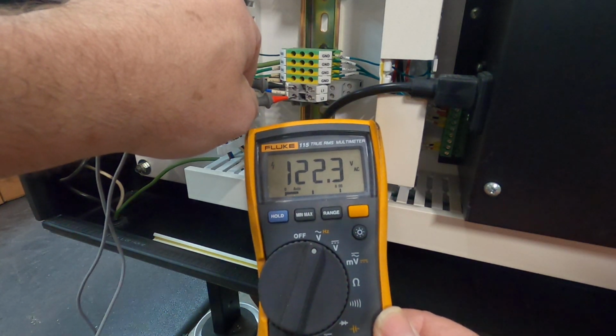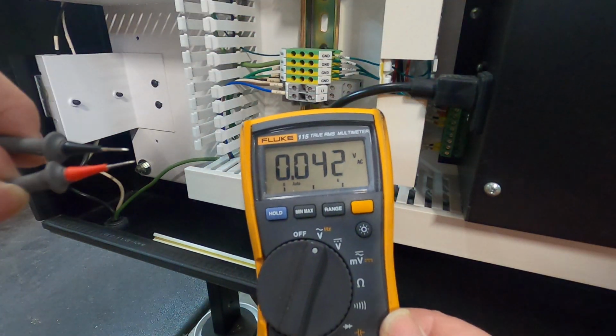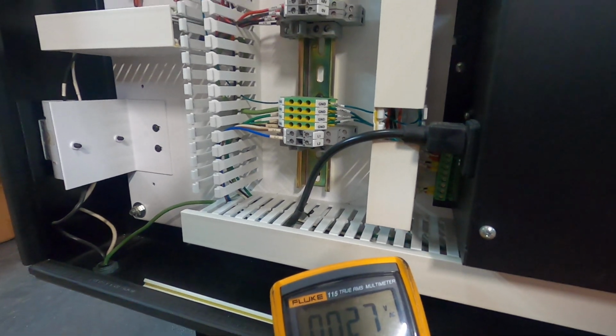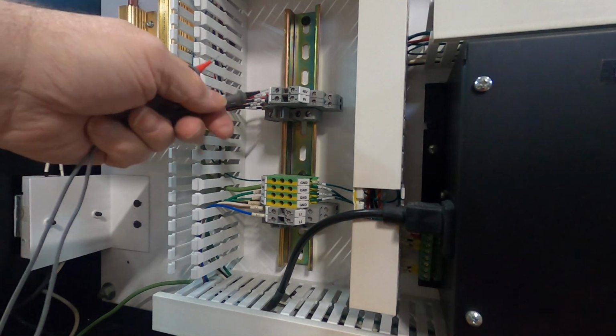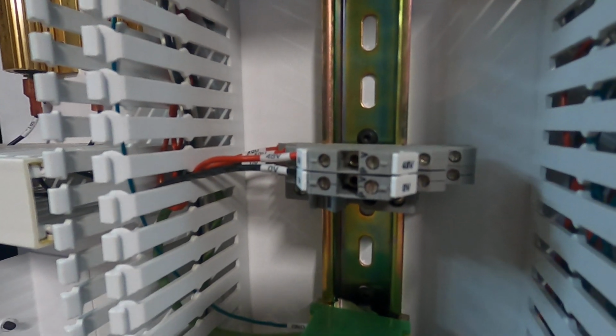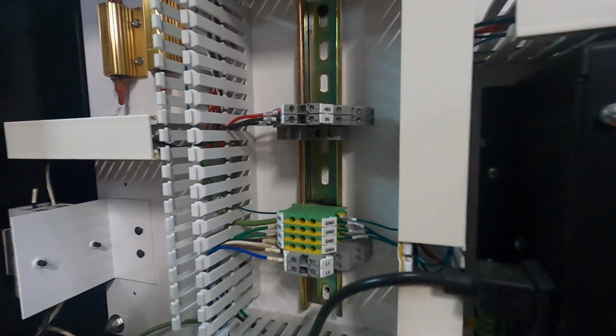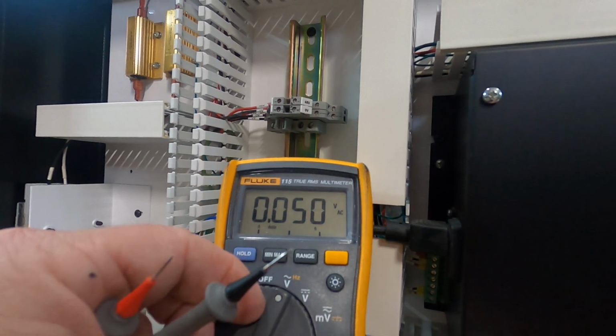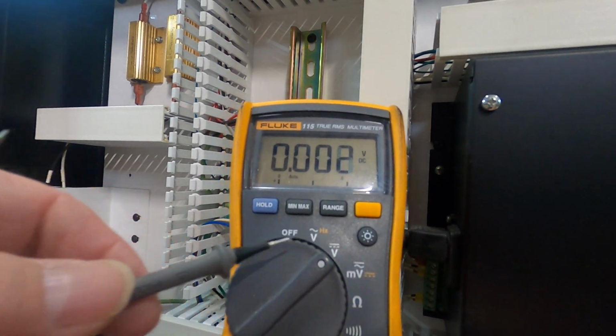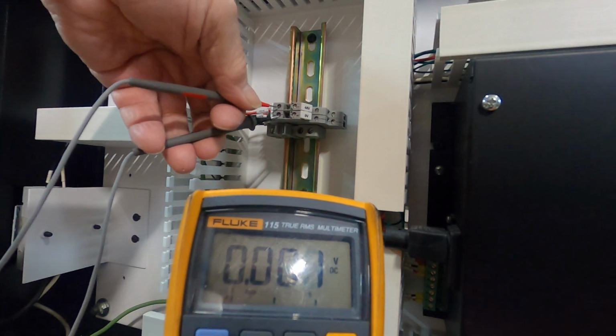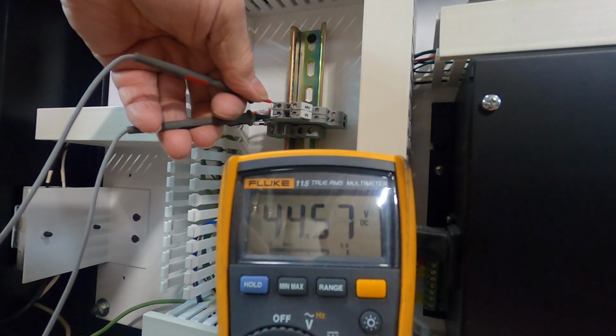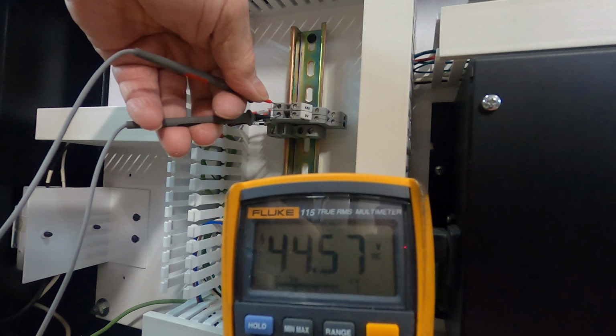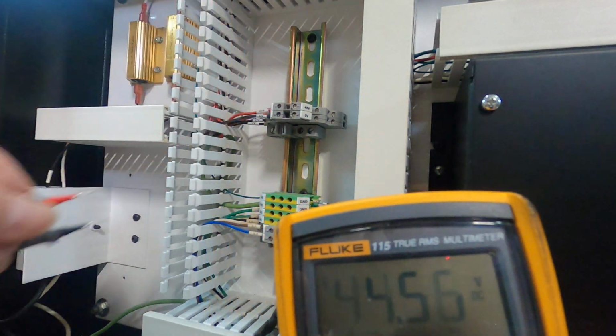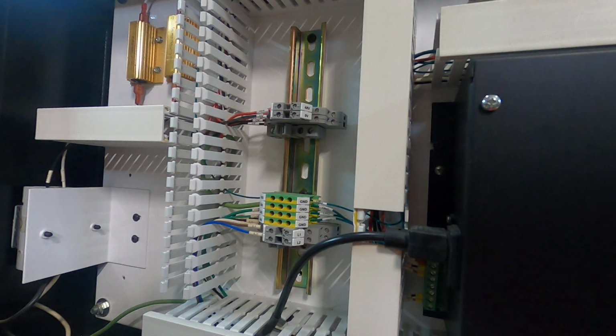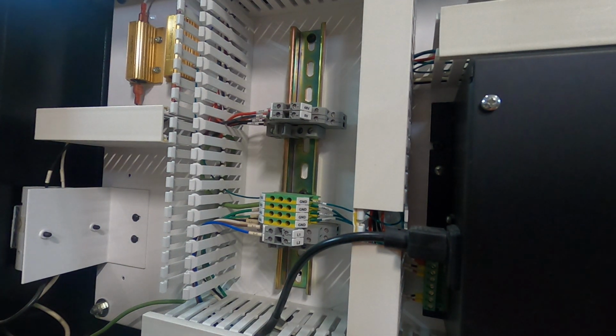All right. Now, if this power supply is working, I should have 48 volts. And if I look up here at these, they say 48 volts and 0 volts DC. So if I turn my meter to DC, which is with the straight line, right? And I put black on 0 volts, and I put red on hot, I should get 48 volts plus or minus 10%. So there we go, 44 volts. Okay. So that means I have power for my motors, because my motors run off 48 volts.